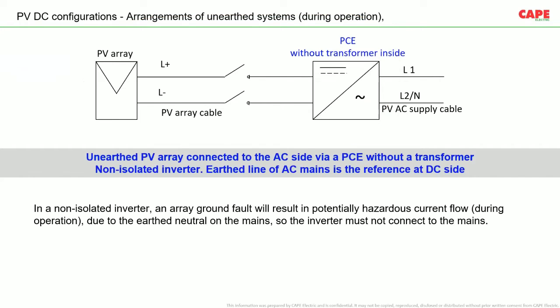Now, under this condition, technically the DC side is electrically connected to the incoming supply because of the neutral earthing of the incoming transformer, of the supply transformer. It can be a supply transformer from the utility company. Unearthed PV array connected to the AC side via a PCE without a transformer, non-isolated inverter. The earthed line of the AC mains is the reference at the DC side.